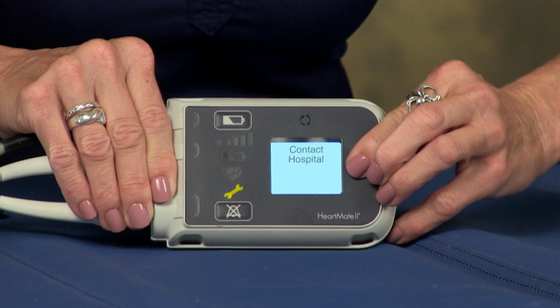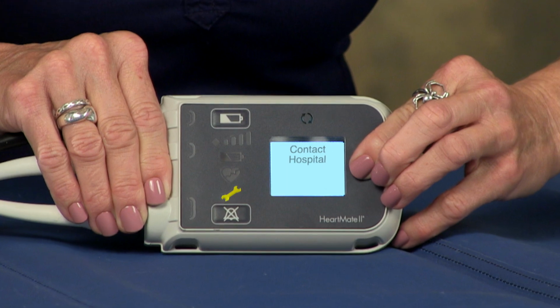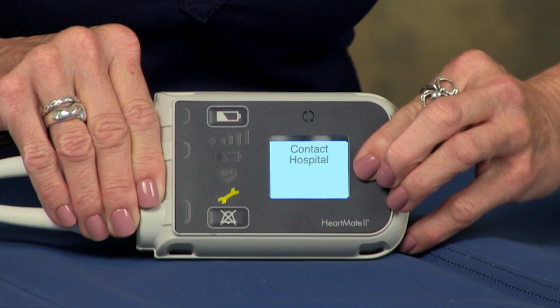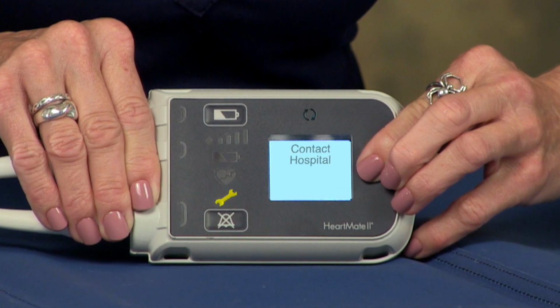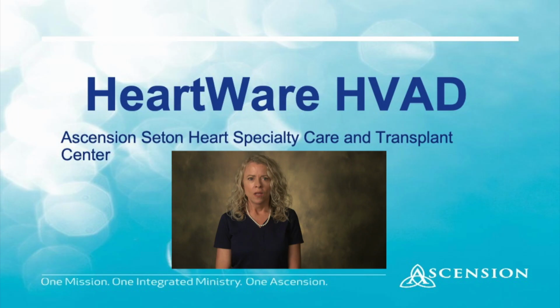Seen less often is a yellow wrench alarm with a message to contact the hospital. It is associated with a controller or driveline problem, and the VAD coordinator will assist you with what to do. This is not a life-threatening alarm. Remember, if the green circle of life is illuminated, the pump is still running, and you can confirm this by auscultating. Now let's look at the Heartware HVAD pump.